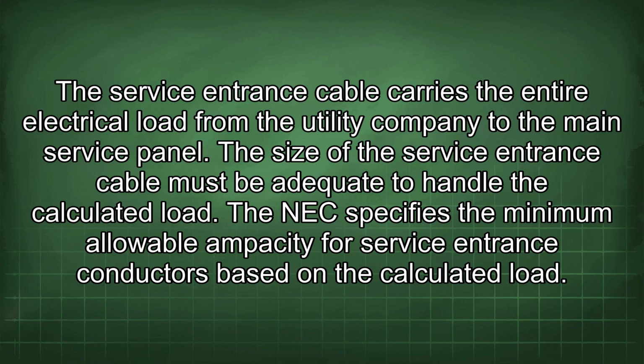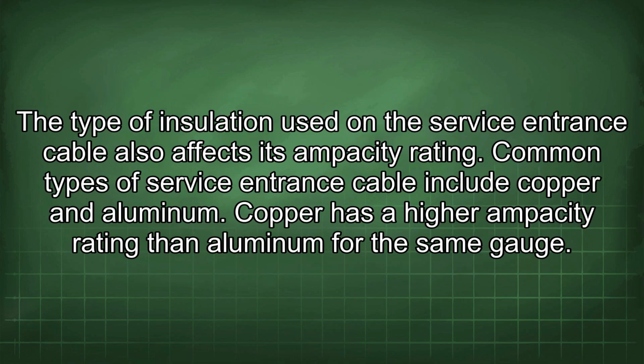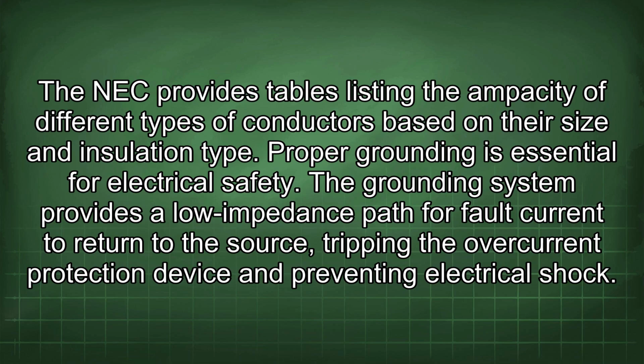The service entrance cable carries the entire electrical load from the utility company to the main service panel. The size of the service entrance cable must be adequate to handle the calculated load. The NEC specifies the minimum allowable ampacity for service entrance conductors based on the calculated load. The type of insulation used on the service entrance cable also affects its ampacity rating. Common types of service entrance cable include copper and aluminum. Copper has a higher ampacity rating than aluminum for the same gauge. The NEC provides tables listing the ampacity of different types of conductors based on their size and insulation type.